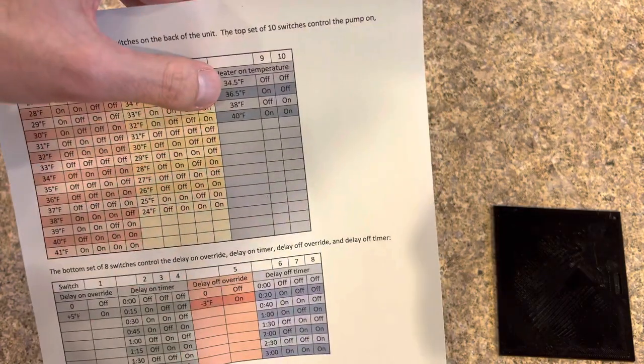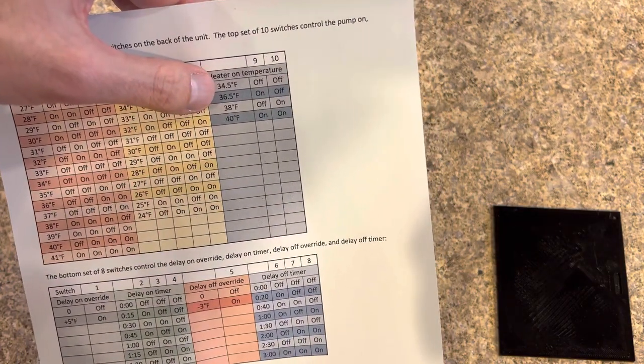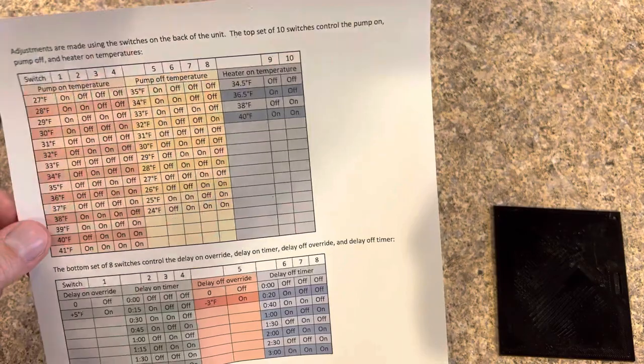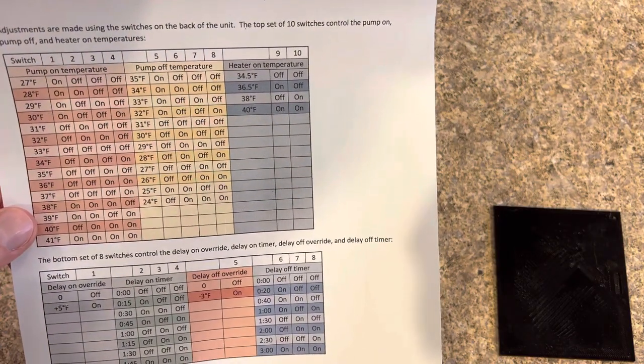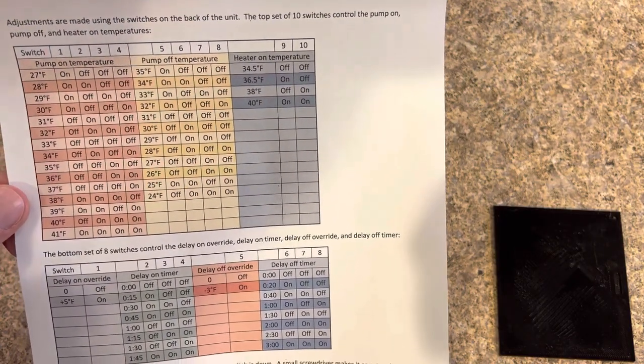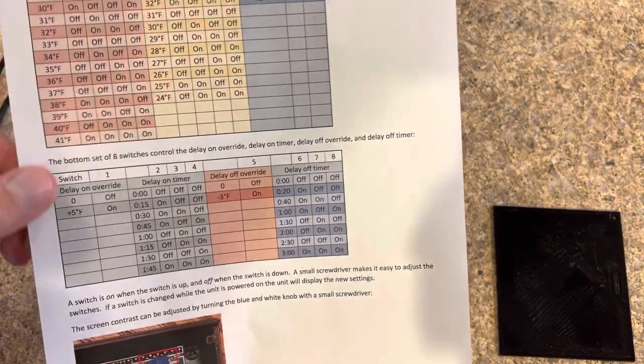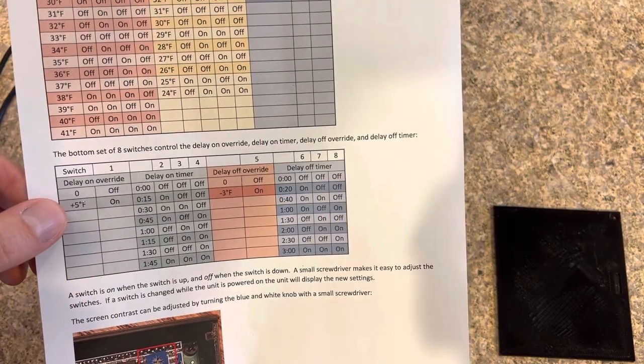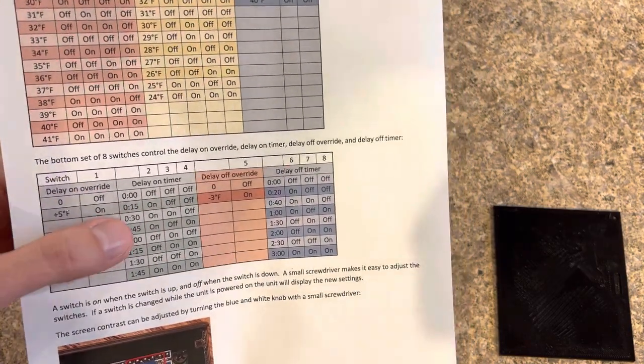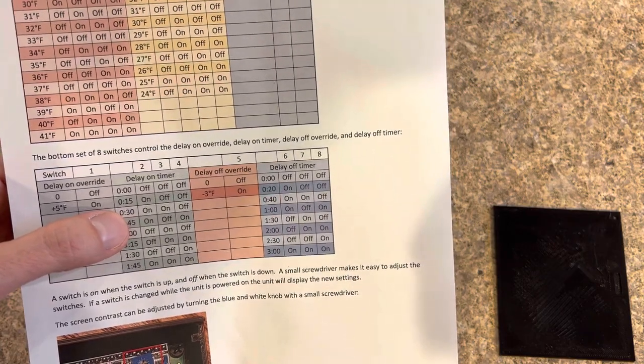The heater can turn on at 34.5, 36.5, 38, or 40 degrees. It automatically shuts off the heater once it raises it one full degree in temperature. And then the second is the delay override. And the best way to explain this is to explain the delay on timer.